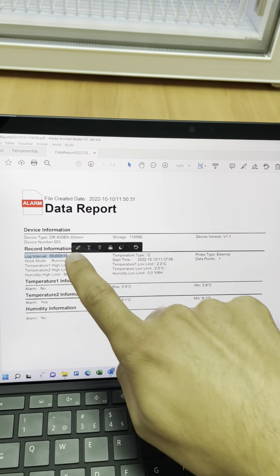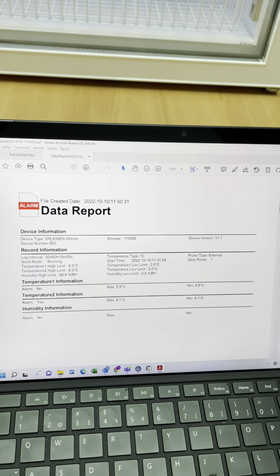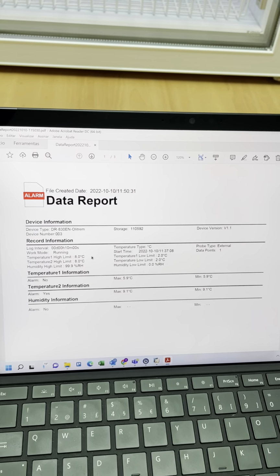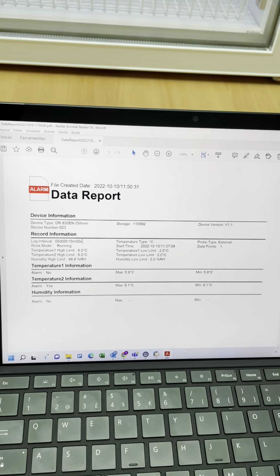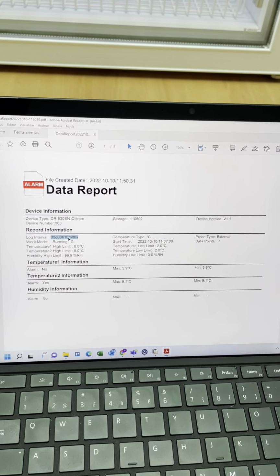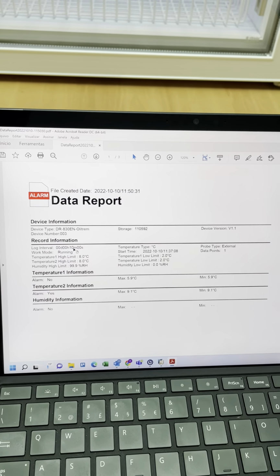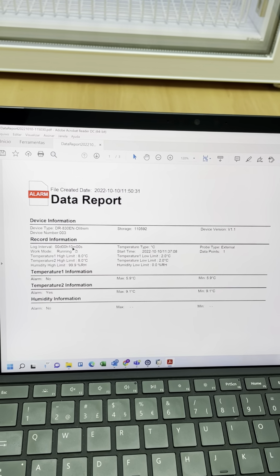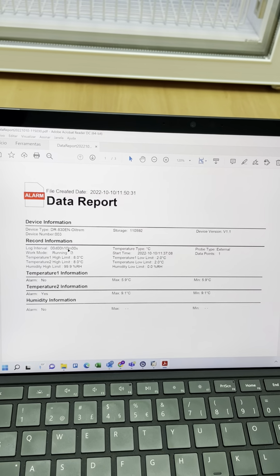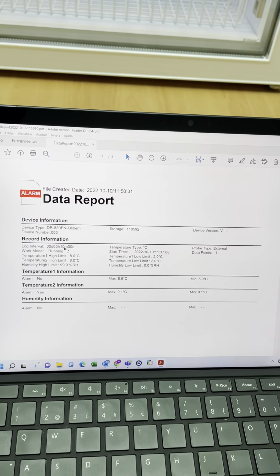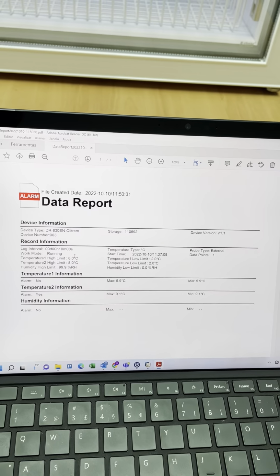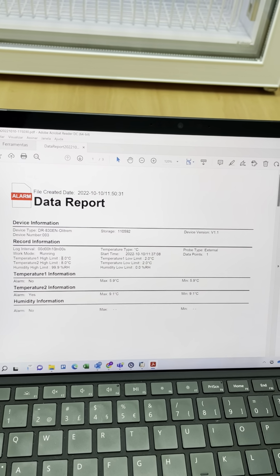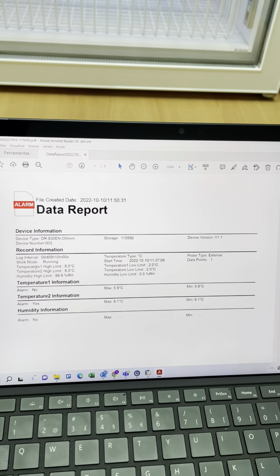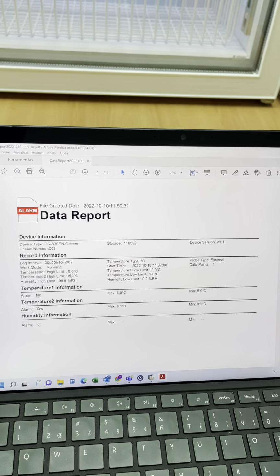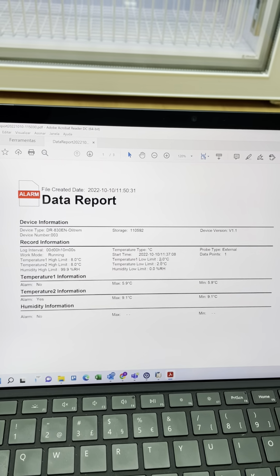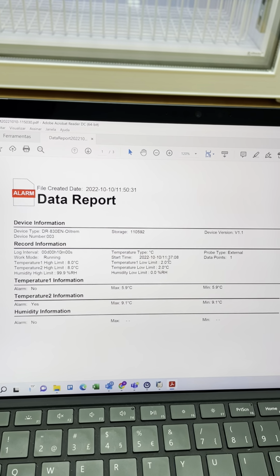In this way you can see this is number 3, so it was from this equipment that we saw first. Here you can see that in this case we have a log interval of 10 minutes, so the controller is recording every 10 minutes, but you can change it in the parameters and set it to work every minute, so recording minute by minute if you want. You see here the temperature alarm, a high temperature alarm of probe 1. Temperature 1 is probe 1, so it is 8, temperature 2 is 8 again also, and the low limit is 2 degrees in all of them.